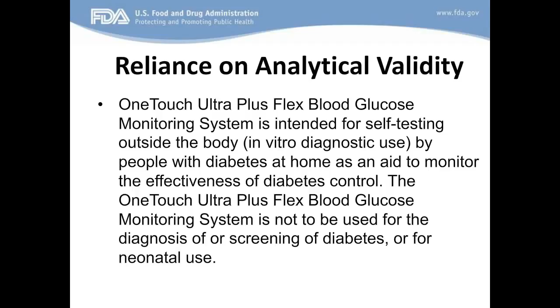Equally so, at least for this meter, the neonatal use requires the ability to measure glucose at levels at which this meter was neither designed nor likely to be accurate, and therefore a warning that this is not for neonatal use is put on. And so here you see a little bit the interplay between analytical validity and clinical validity, because if the meter itself cannot go down to the levels that are necessary for neonatal use, then the clinical validity for that meter has not been determined, but is purely determined by the analytical validity that we look at.